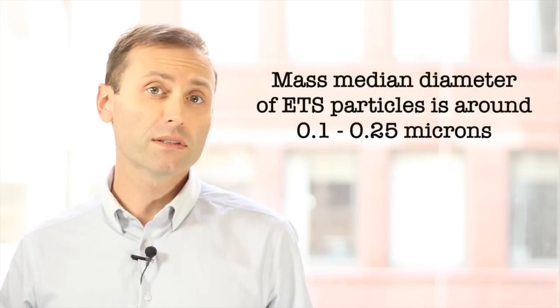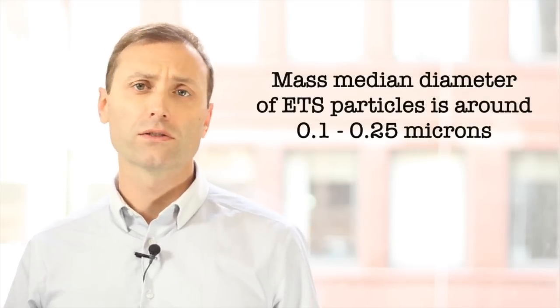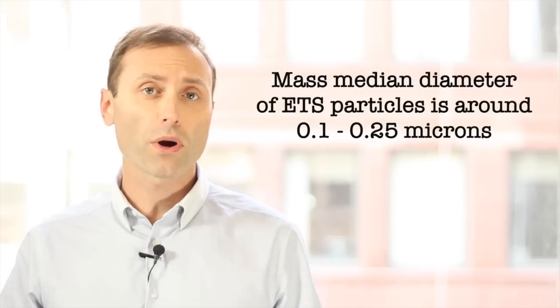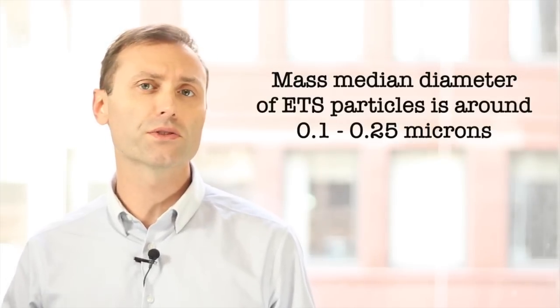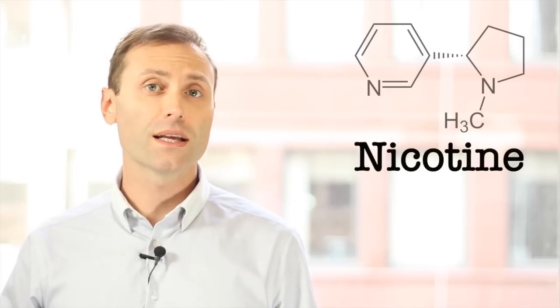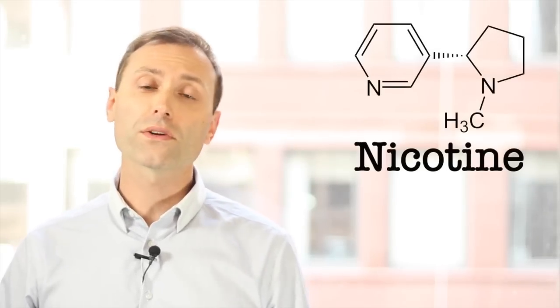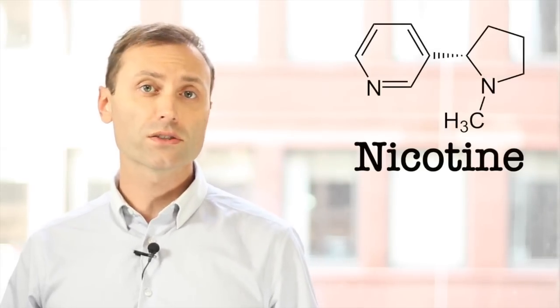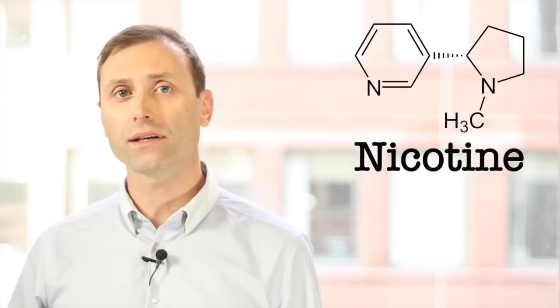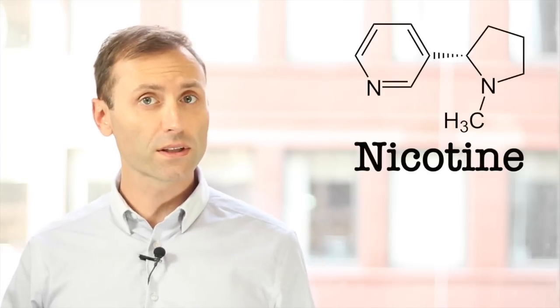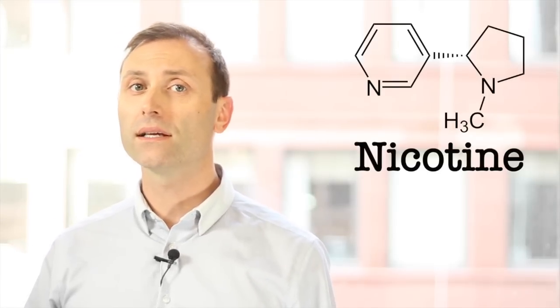The mass median diameter of ETS particles is around 0.1 to 0.25 microns, so particle counters should be selected that can detect those fine particles. Nicotine is a highly specific marker without other common indoor sources. Several large studies have been performed using nicotine as the surrogate. Because it will condense on surfaces, air and surface samples may be needed to collect it. Others use carbon monoxide or specific VOCs as surrogates. And of course, the human nose is pretty good at detecting cigarette odors if a subjective evaluation is allowable.